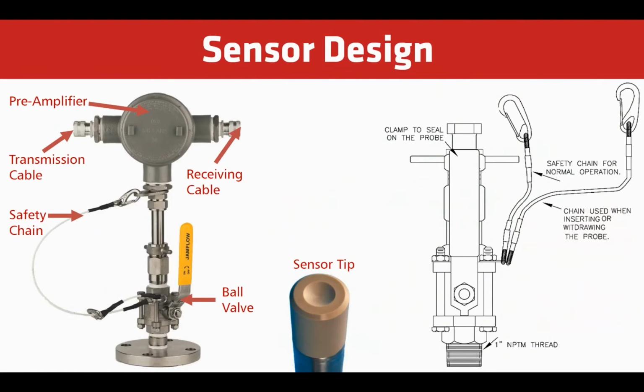So the way you would pull this out is have the safety chain on the long setting, pull it out. It gets just past the ball valve, so no sample leaks out. Close the ball valve, and now you can take the probe completely out of the gland fitting, and you could put it in a bucket of known standard water to do a quick QC test. Or if you wanted to do, call it quarterly maintenance, take a rag and wipe the sensor tip clean, and then just in reverse order, install it back in with the valve open once it's in the gland, and then go down to the holding point, which is the short portion of the chain where it secures the sensor at the depth that we want in that sample pipe.